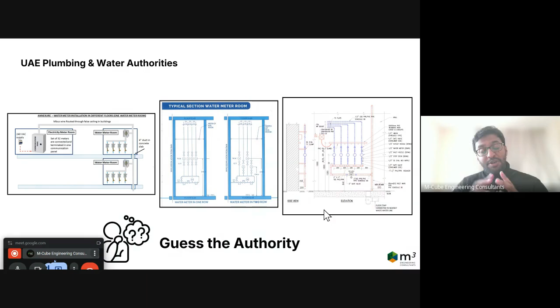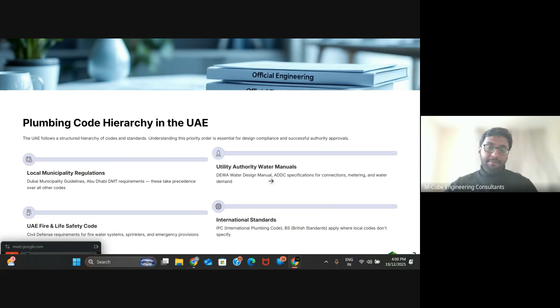Moving forward, we have the plumbing codes hierarchy in UAE. Again, you have local municipality regulations for the plumbing code, which come from the parent code, the International Plumbing Code (IPC). You also have the British Standards, and from ASPE, the American Society of Plumbing Engineers. All these codes are integrated, and then the local regulations are formed. Especially in plumbing codes, there's also an interrelationship with fire life safety, because of the fire water demand requirement. We'll see later the relationship between how these regulations combine and how we estimate water demand. But in general, this is how the hierarchy of plumbing codes works here in UAE.